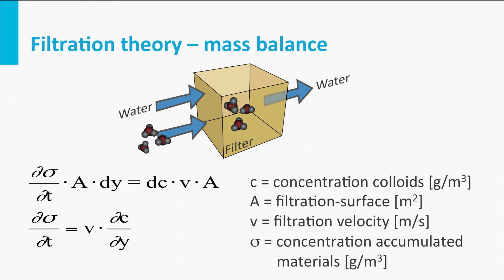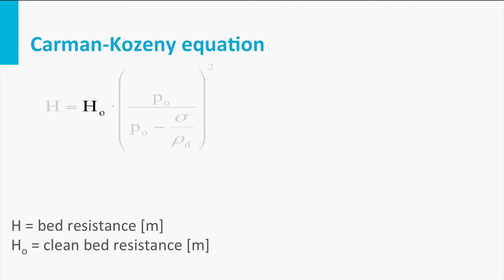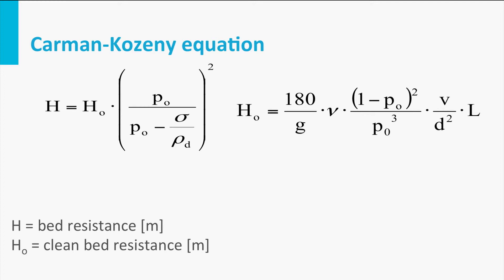Based on the accumulation of solids in the bed and the clean bed resistance, the bed resistance of a clogged filter can be calculated. The clean bed resistance is determined by the famous Carman-Kozeny equation, giving a relation between the resistance and the filtration velocity, the porosity, the grain size, the viscosity, and the filter bed height.